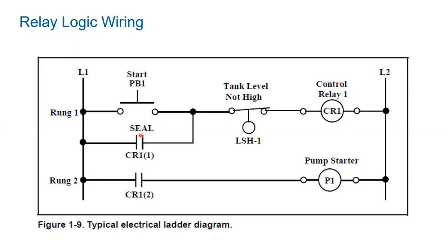Now we have what's called a seal circuit here, also known as a seal-in or a latch circuit. The problem is that most of the push buttons we use are momentary push buttons, meaning they're spring loaded. When I press it and take my finger off of it, it opens up again. They're not maintained push buttons, right? You've pressed a push button before where, when you press in on it, it locks in, and you press it again and it pops back out. That would be a maintained push button. But a push button like you'd have on your keyboard is a momentary push button, right? The minute you take your finger off the push button, on a keyboard, it goes back up again. It's got a little spring in it that pushes it back up.